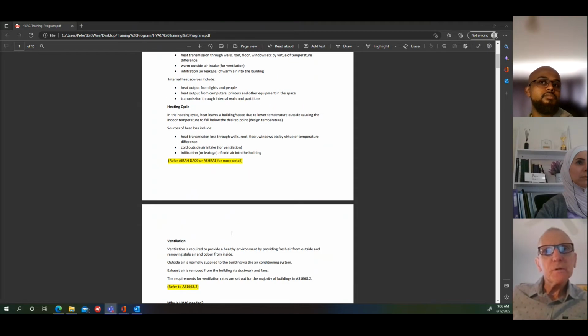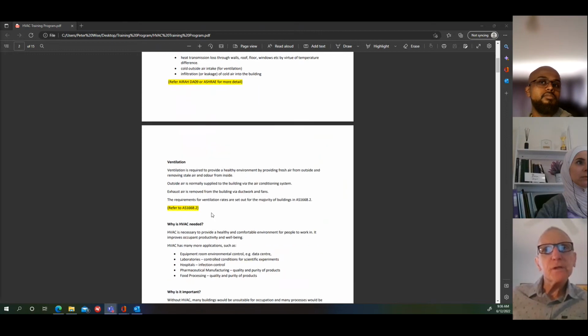Ventilation is required to provide a healthy environment by providing fresh air from outside and removing stale air and odour from inside. So the basic things that we do every day of the week are outside air intake, which is a requirement of AS 1668 Part 2, and toilet exhaust. Most buildings have that, where we have to take that stale air from the toilets and discharge it outside.